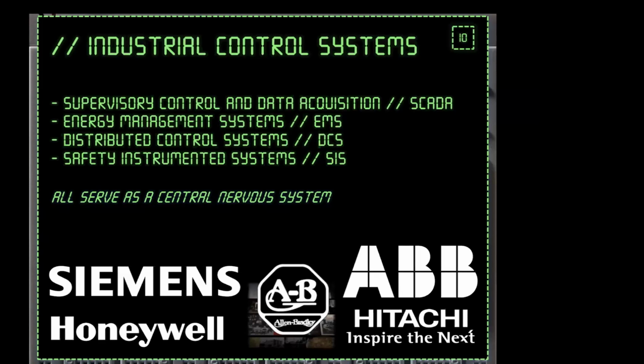Supervisory control and data acquisition systems, that's the one we just walked through and built together. Supervisory control and data acquisition systems are typically just called SCADA, and they offer two main functionality components. The first is the supervisory control, which we put together all the way up to the HMI, so your PLCs connected to sensors and actuators, kicking information up to an HMI.